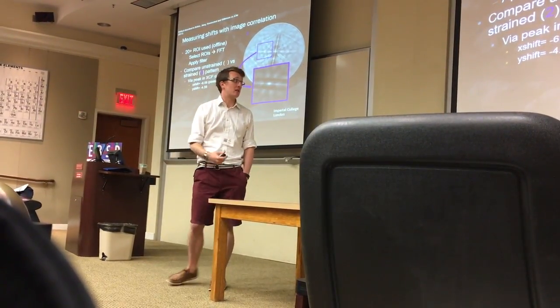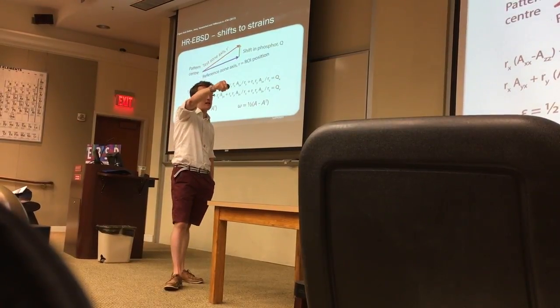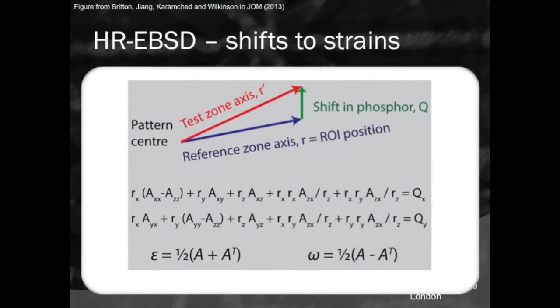Why do I need sub-pixel precision? Because the shift on the phosphor is related to components of my strain tensor and how far my sample is from the detector. If I have 1000 pixels and only 1-pixel sensitivity, I won't get 10 to the minus 4 strain — a 1-pixel deviation gives you 10 to the minus 3. A tenth-of-a-pixel deviation gives you 10 to the minus 4. A little math relates the position of measurements to shifts on the diffraction pattern, extracting strain tensor components A_X, A_Y, etc.